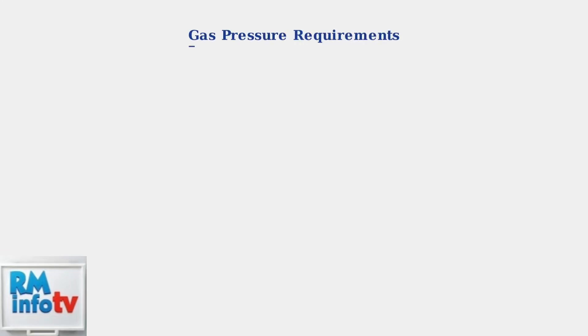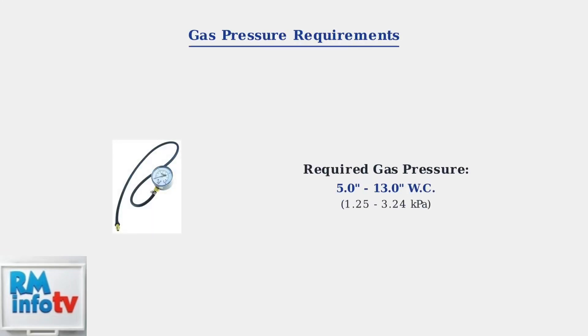Next, check the gas pressure using a manometer. The gas pressure should be between 5.0 and 13.0 inches of water column, which equals 1.25 to 3.24 kilopascals. Inconsistent pressure can trigger error code 13.